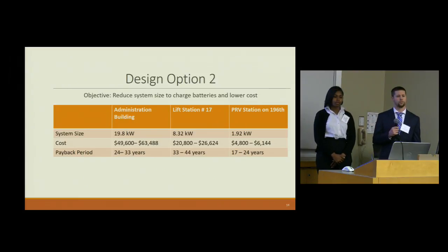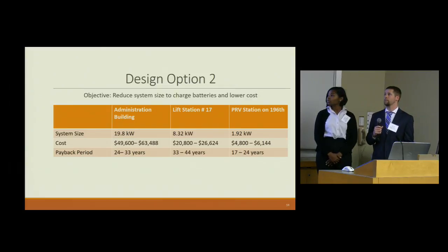You may have noticed that for lift station 17 and the PRV station, the system size for design option 2 is actually bigger than design option 1, because the site itself doesn't have enough real estate to install enough solar power to charge 3 days worth of batteries in 1 day. This design option needs more refining, but that requires a more thorough analysis for each of the 22 sites, which we did not have time to complete.